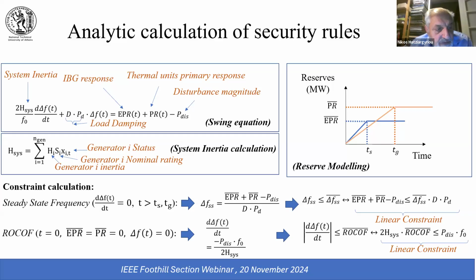Similarly, you can find the rate of change of frequency, which happens at t equals 0 immediately after the disturbance. There you assume that your reserves have not been mobilized yet, so delta f at t equals 0. Again, by solving this equation, you can linearize the rate of change of frequency problem, as a function of the disturbance and also of your system inertia, and it can be used as a constraint in your dynamic unit commitment problem.